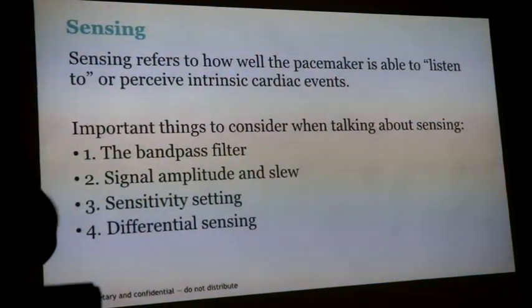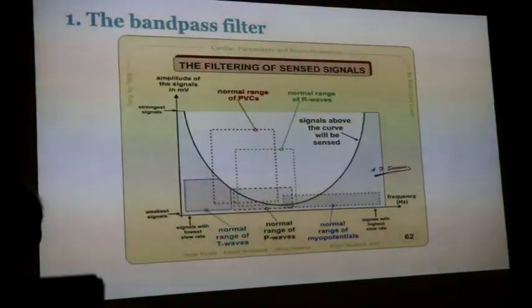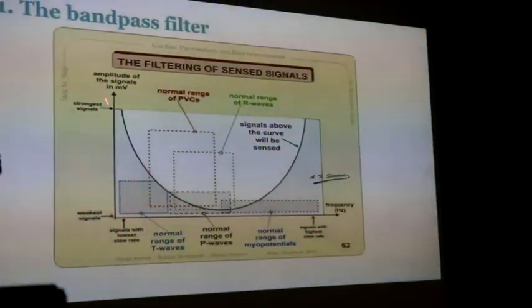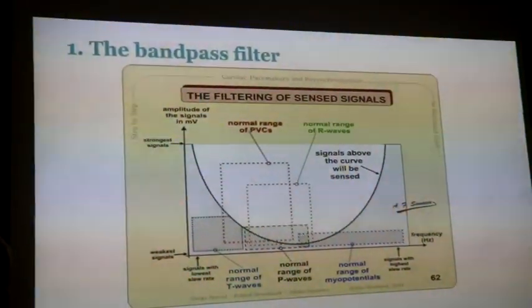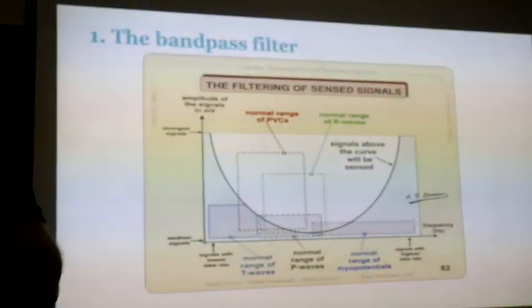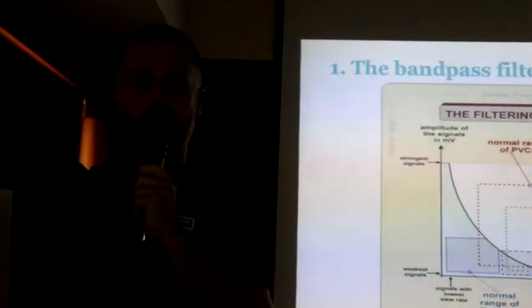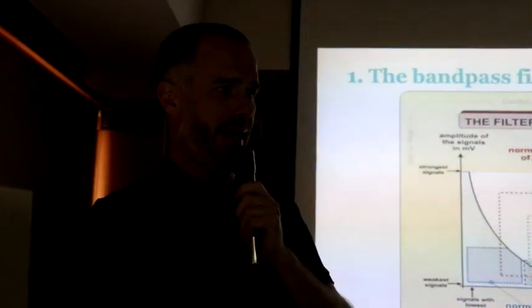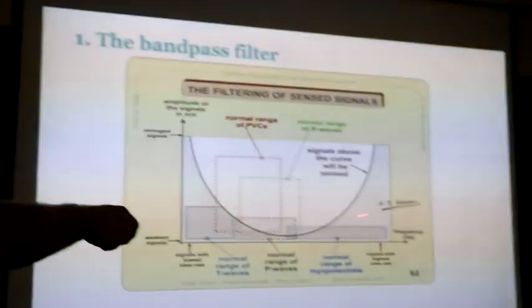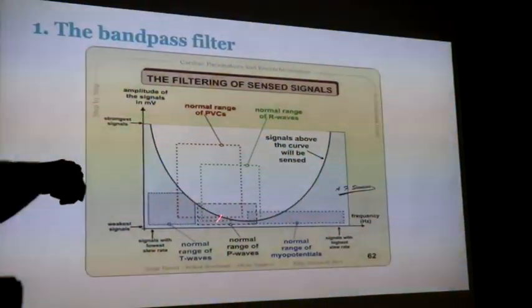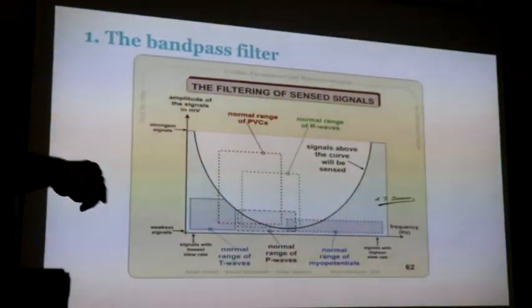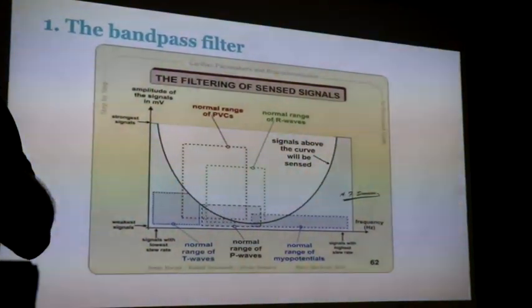The bandpass filter is built into the pacemaker, and it is a mechanism of filtering out stuff that we don't want to see. If you look at the raw signal from a pacemaker lead, without putting it through the bandpass filter, it would look like loads of very high frequency noise going up and down like this, and you would ask, what do I do with that? The bandpass filter filters out respiratory swing. This side of the filter filters out slow moving things, and this side filters out very high frequency stuff like skeletal myopotentials.